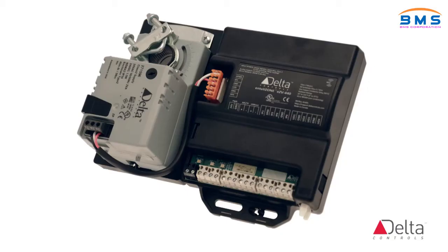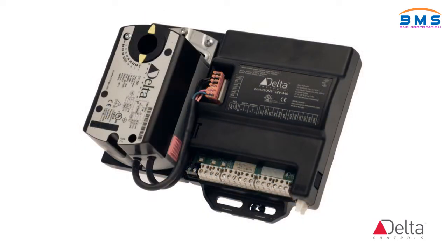The enteliZONE VAV is a BACnet MSTP controller designed specifically for VAV and VVT applications. It has a built-in control algorithm for both VAV and VVT applications, but it also has the ability to add GCL programming, which gives you the ability to customize. Say there's something you need to change in the application. You can use the GCL to customize it, but not have to rewrite the entire application. So you can selectively override the configurable algorithm.